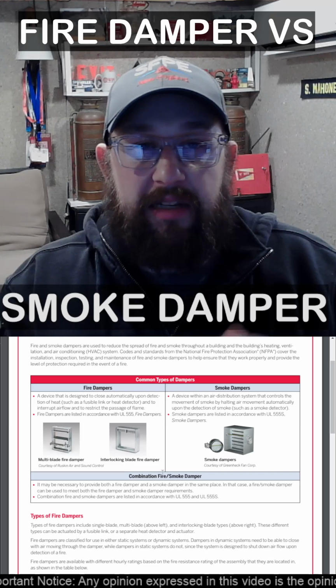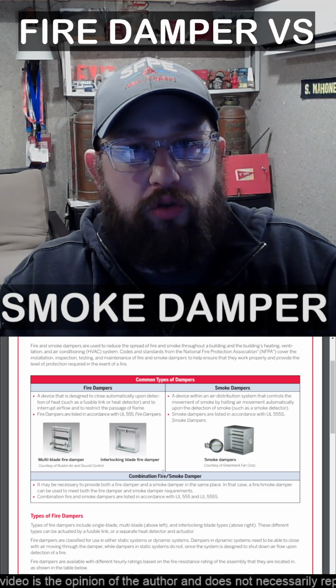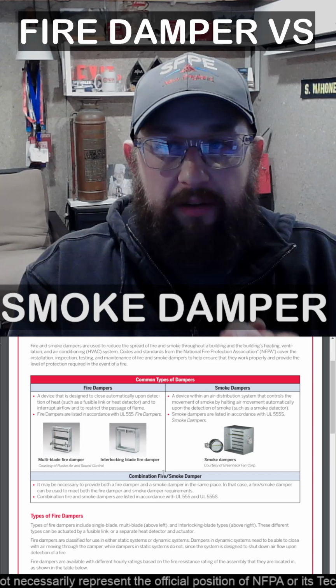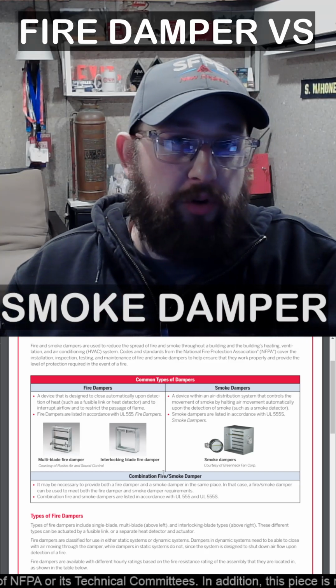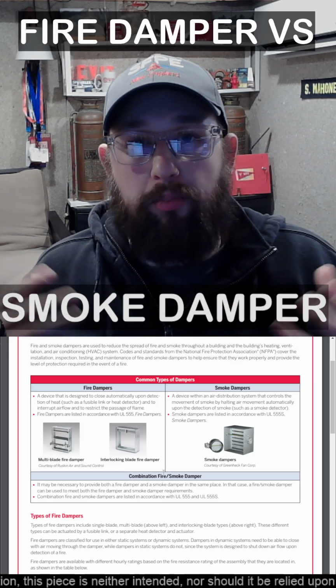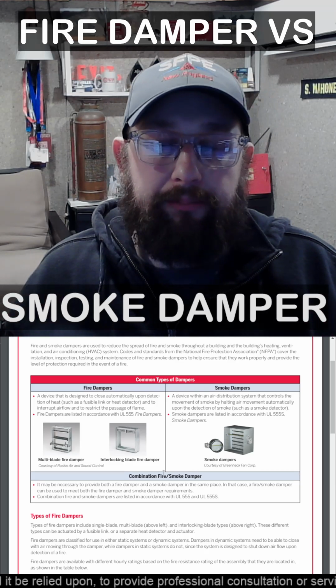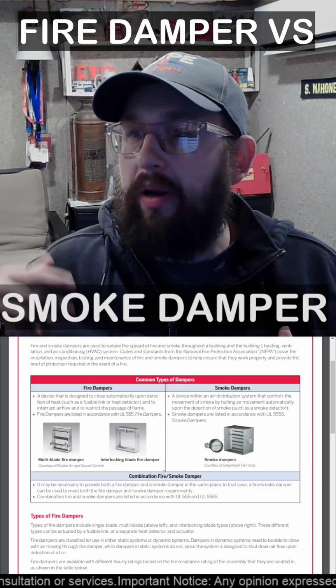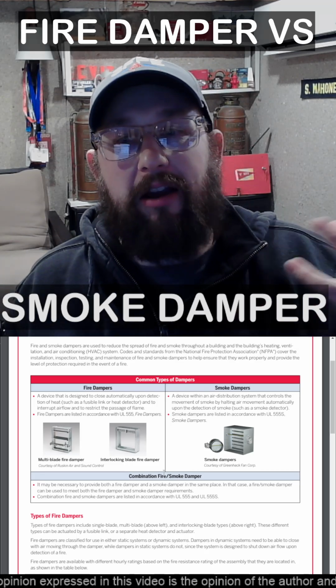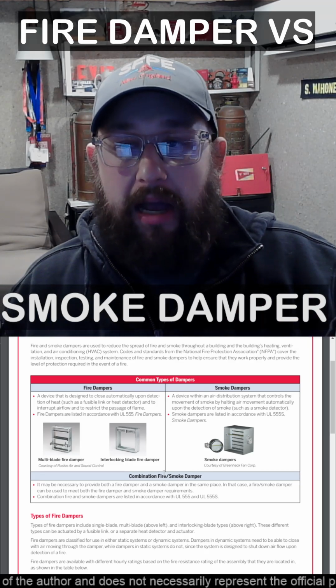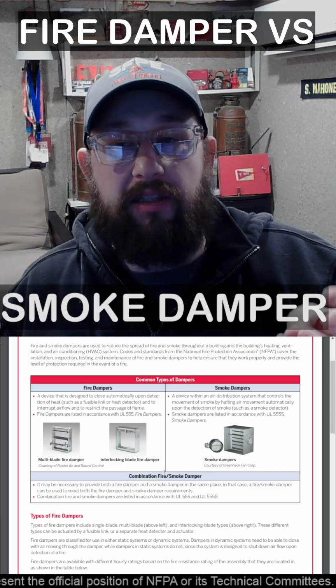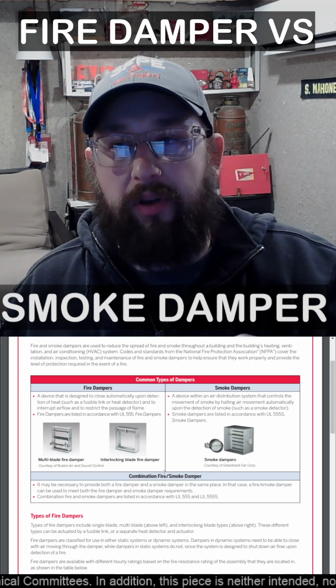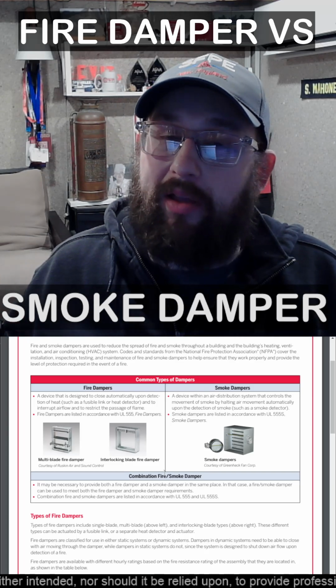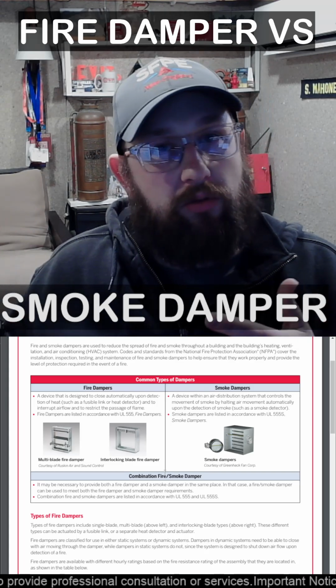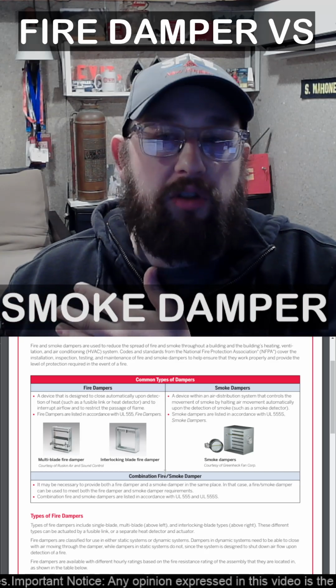Now, the main difference here: a fire damper is used to limit the spread of fire, while a smoke damper is used to limit the spread of smoke. They're both going to be installed in air transfer openings or within ducts, but a fire damper is going to be actuated based on heat, and it's designed to stop fire from moving, while a smoke damper is going to close upon the detection of smoke, and it's just limiting that spread of smoke.